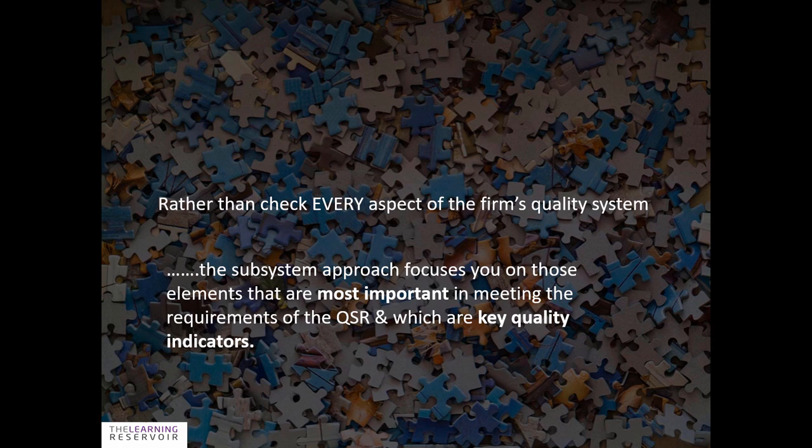For CAPA, key quality indicators include: how many open CAPAs do you have — do you have a hundred or do you have five? How many closed ones do you have? How long do your CAPAs remain open — are they open for ten months or three months? What's the trend? Have you reopened CAPAs for some reason? That wouldn't be good, because it's telling you that you didn't get to the root cause of the problem. Are there repeat issues with CAPA? So those are the key quality indicators.